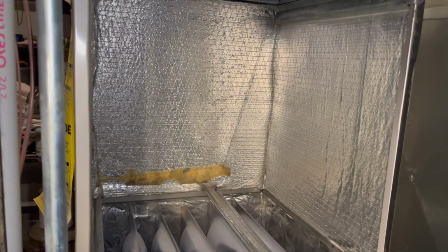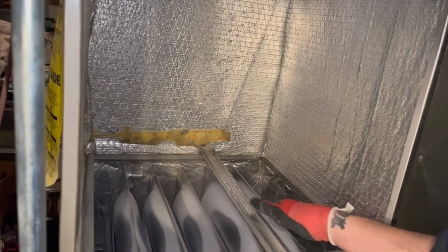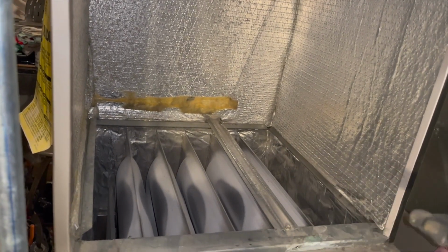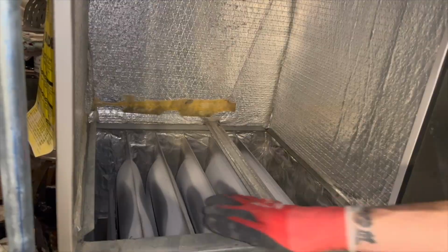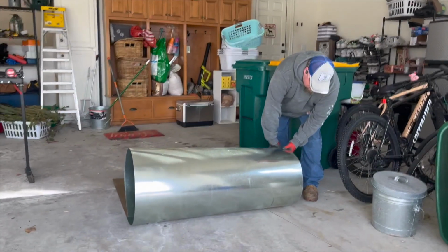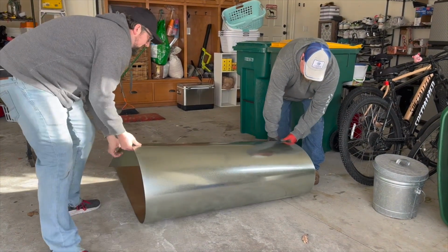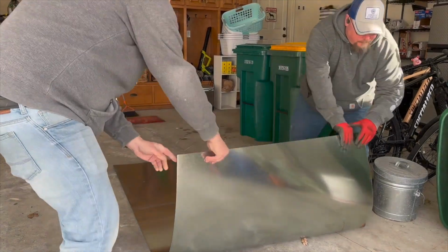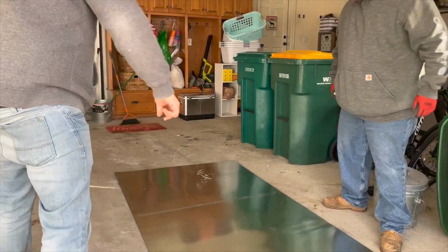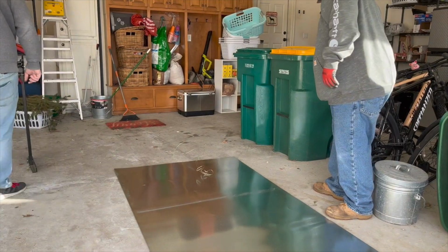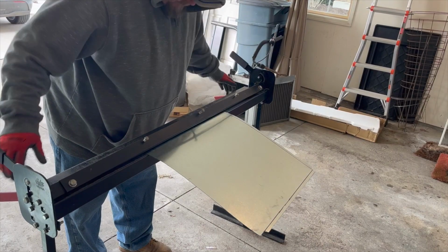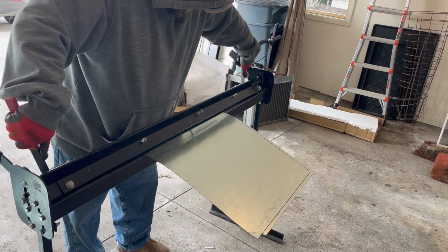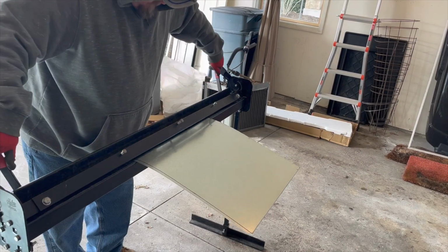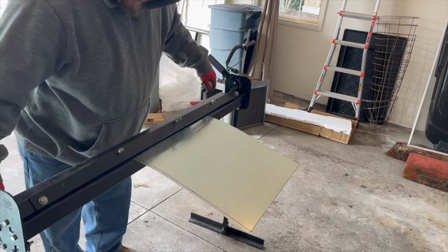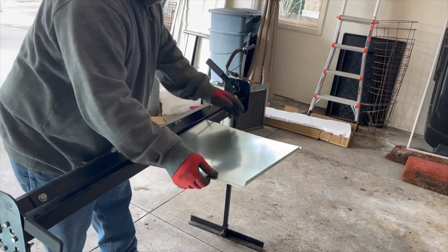Now you saw when we pulled the coil out that there was a little horizontal brace inside the unit. That's not going to hold up our new coil. We have to build something a little more significant. Most contractors, when they come to your house to do a retrofit, have to do a little bit of sheet metal work for the retrofit. So they'll bring in this little metal brake and some hand tools in order to accommodate the sheet metal changes. This contractor is going to make a little pan for the coil to sit in inside the existing casing.